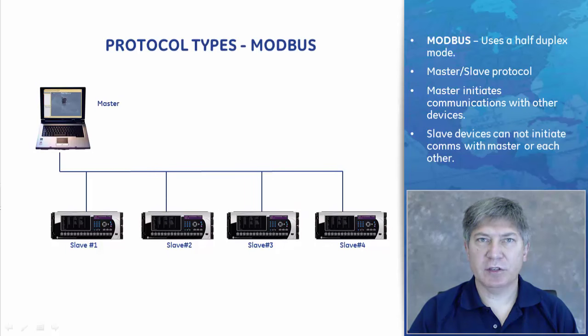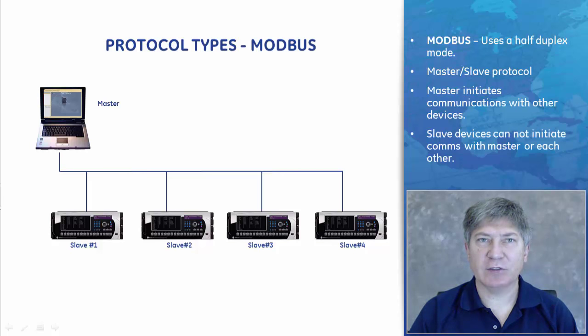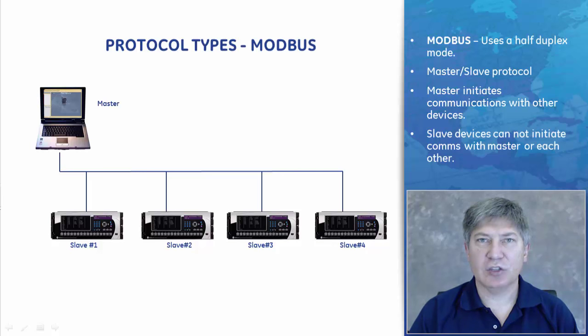In North America, Modbus RTU has traditionally been the most popular protocol used in industrial power applications. Modbus uses a half-duplex mode utilizing a master-slave protocol. There is one master on the LAN and multiple slaves. Each slave is assigned its own slave address. The master initiates communications using the unique slave address, or can send a command to all slaves using broadcast address 0. In Modbus, the slaves cannot initiate communications with the master or each other.